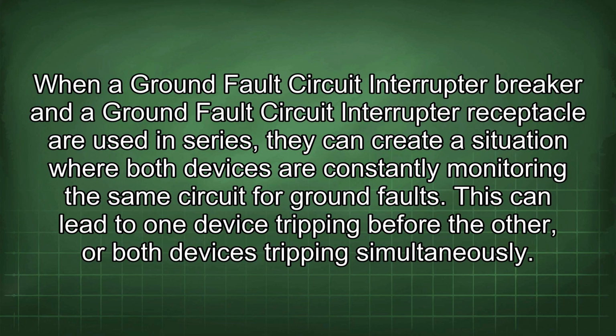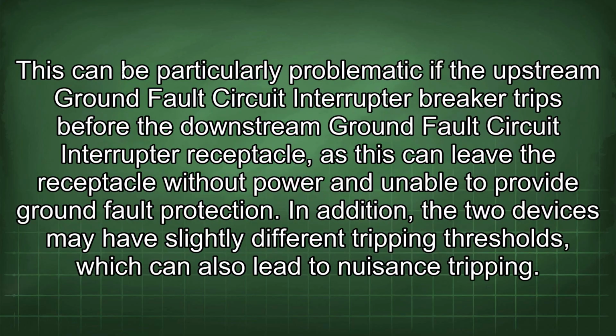When a ground fault circuit interrupter breaker and a ground fault circuit interrupter receptacle are used in series, they can create a situation where both devices are constantly monitoring the same circuit for ground faults. This can lead to one device tripping before the other, or both devices tripping simultaneously. This can be particularly problematic if the upstream ground fault circuit interrupter breaker trips before the downstream ground fault circuit interrupter receptacle, as this can leave the receptacle without power and unable to provide ground fault protection.